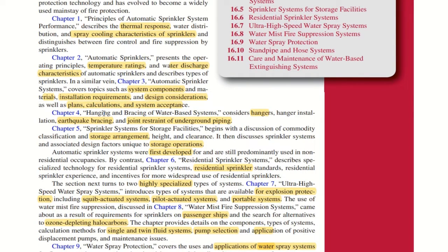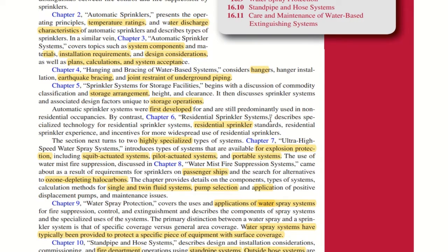Chapter 4 refers to hanging and bracing of water based systems, which covers hangers and supports, etc. Chapter 5 is related to sprinkler systems for storage facilities. In this we shall discuss commodity classification, storage arrangements, and heights and clearances requirements. Chapter 6 is dedicated to residential sprinkler systems, which covers residential sprinkler standards and types of residential sprinklers, etc. Chapter 7 refers to a highly specialized type of system, ultra high speed water spray systems, which is available for explosion protection, and there are various systems included in this, such as squib actuated systems, pilot actuated systems, and portable systems.